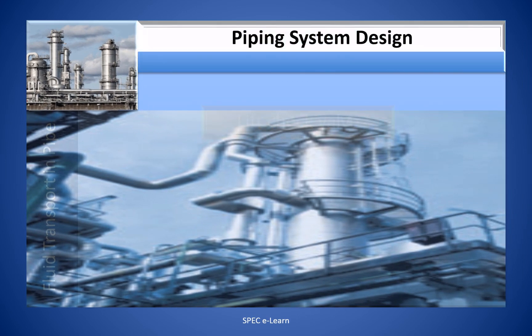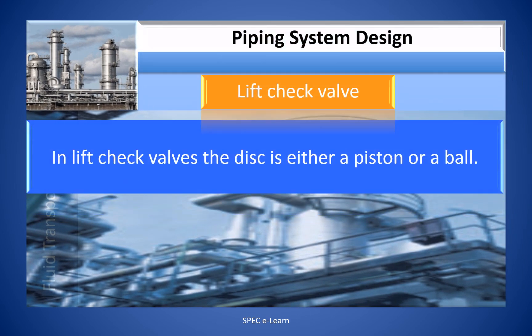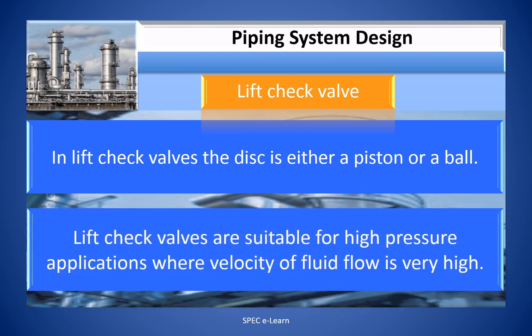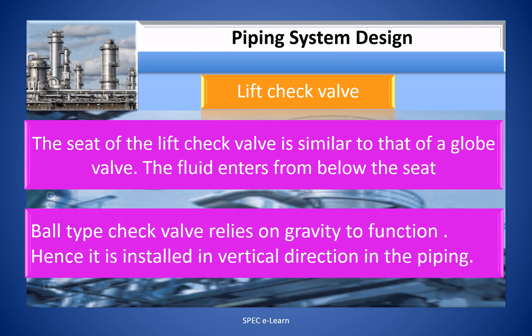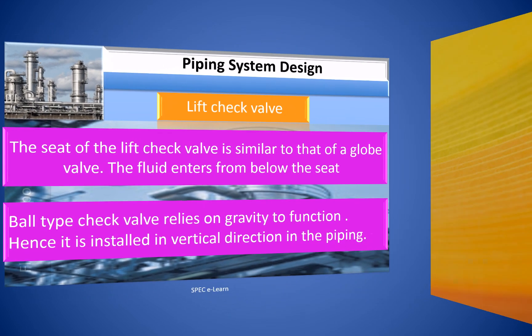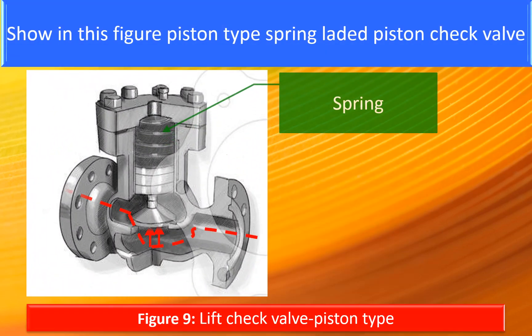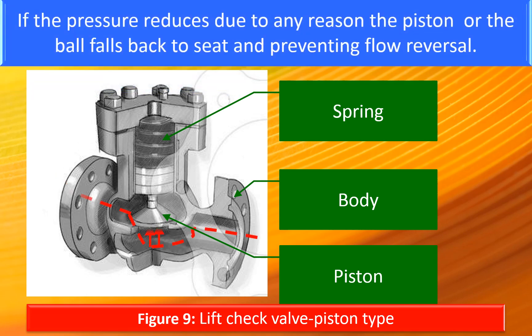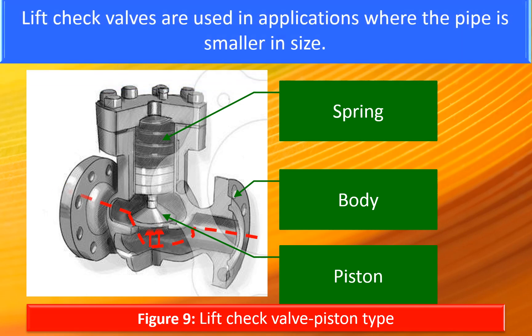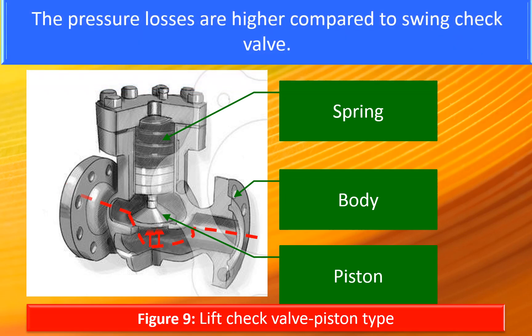In lift check valves, the disc is either a piston or a ball. Lift check valves are suitable for high-pressure applications where the velocity of the fluid is very high. The seat of the lift check valve is similar to that of a globe valve, and the fluid enters from below the seat. The ball-type check valve relies on gravity to function and is installed in a vertical direction in the piping. Once the minimum fluid pressure is attained, the pressure lifts the disc and allows liquid to flow. If the pressure reduces for any reason, the piston or ball falls back to the seat, preventing flow reversal. Lift check valves are used in applications where the pipe is smaller in size; pressure losses are higher compared to the swing check valve.